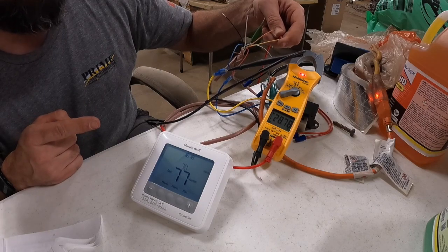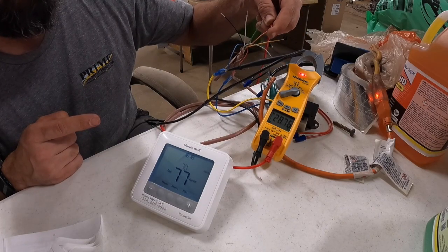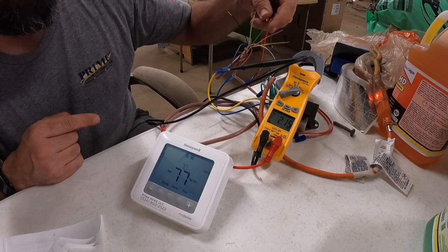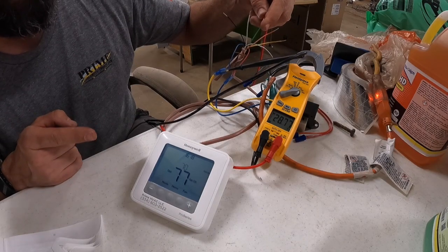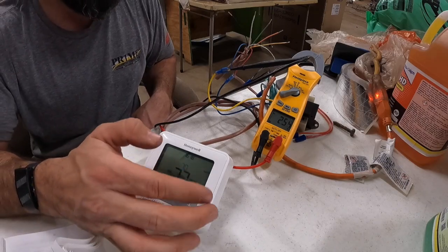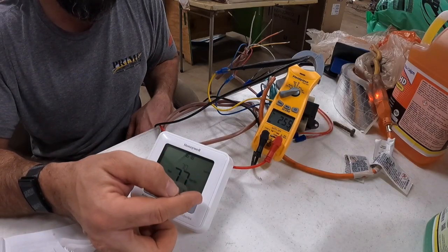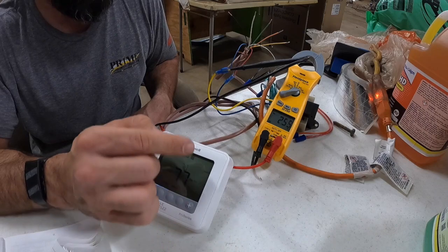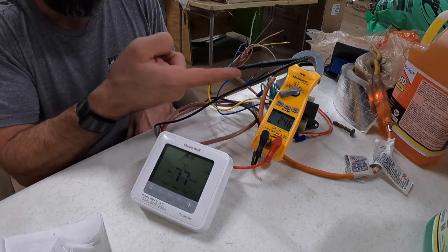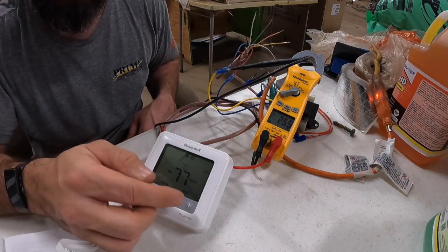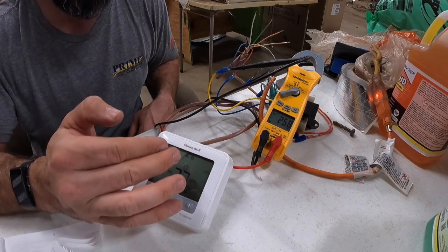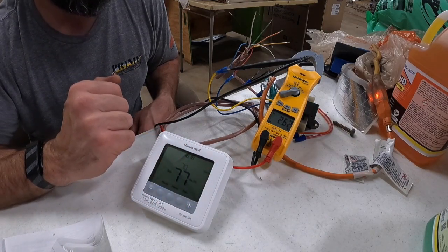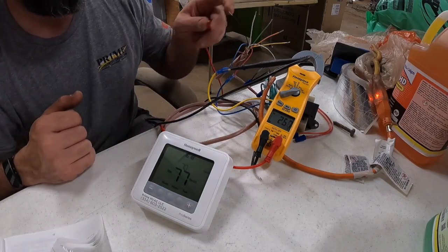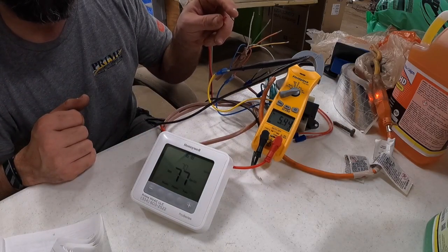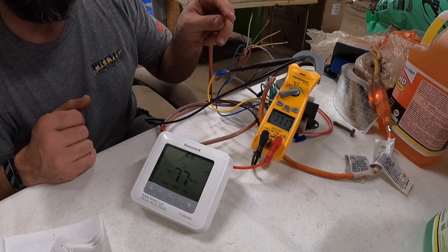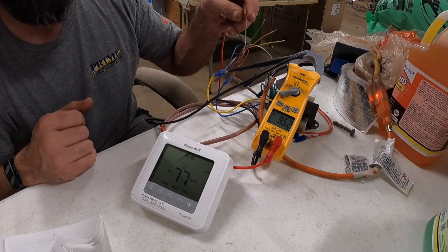We're getting 28 volts on Y. We're getting 28 volts on O. And we're getting 28 volts on G. So that thermostat is taking the power that's coming in to the R terminal from the red wire, which is right here, which is what the hot from the transformer is connected to, and it's directing that voltage to each of those terminals when you call for cool. And we're not getting 24 volts on the heat strips, as we shouldn't.